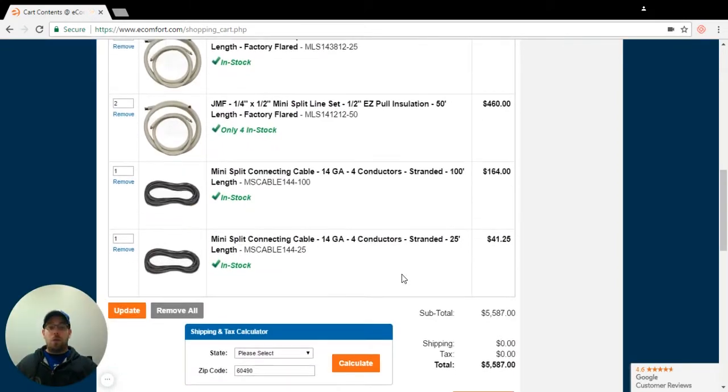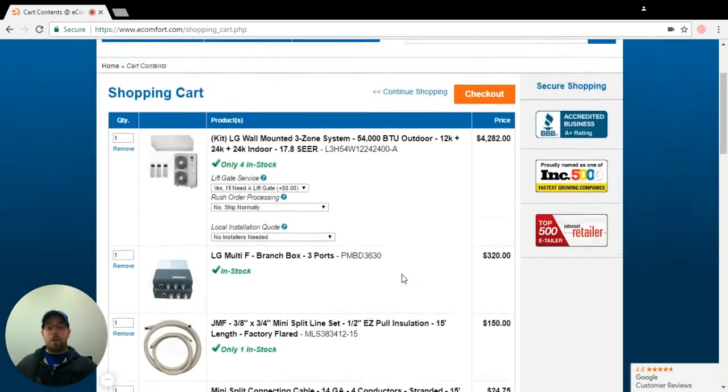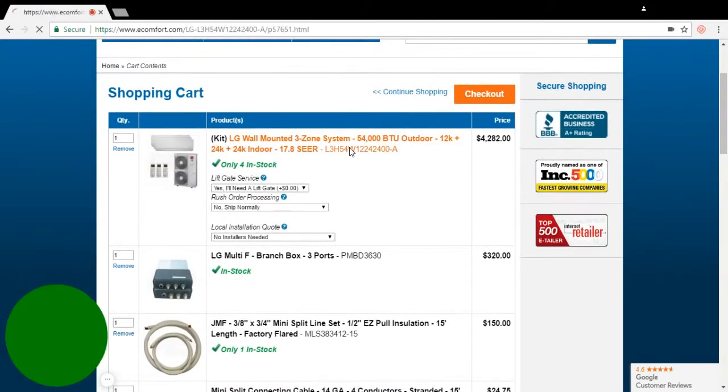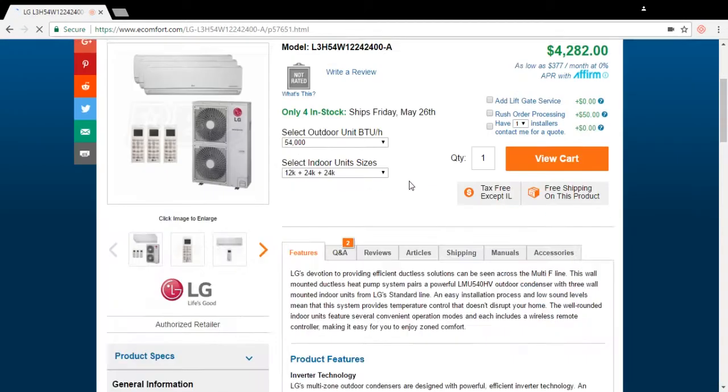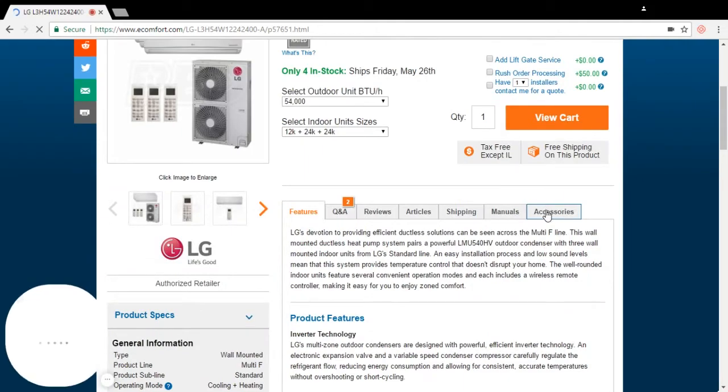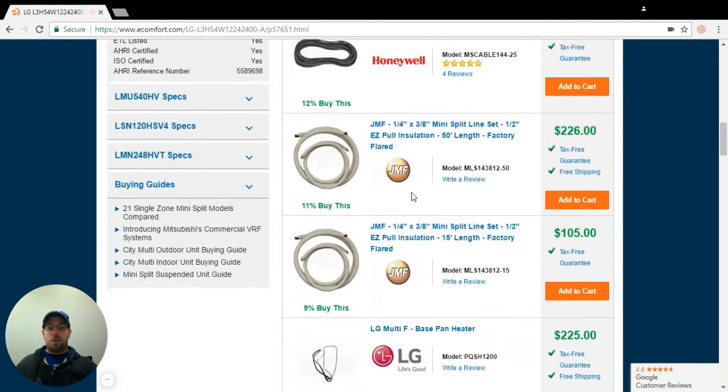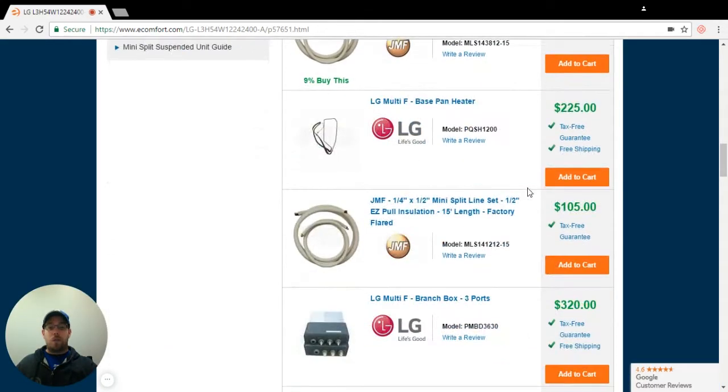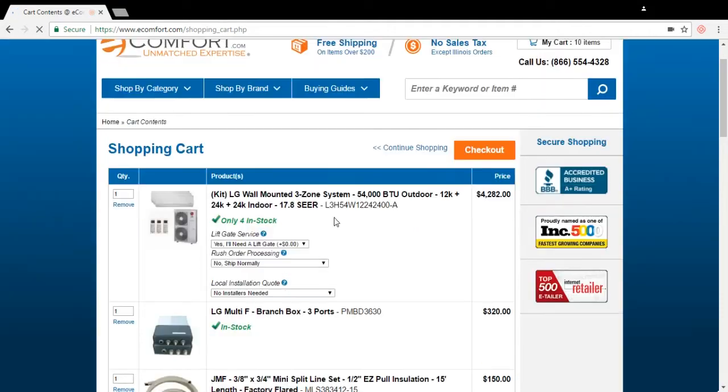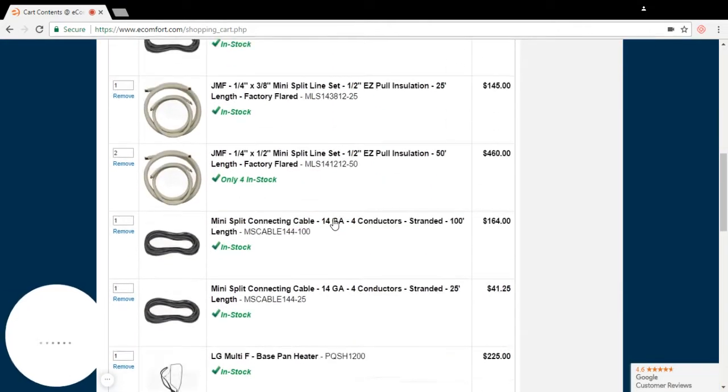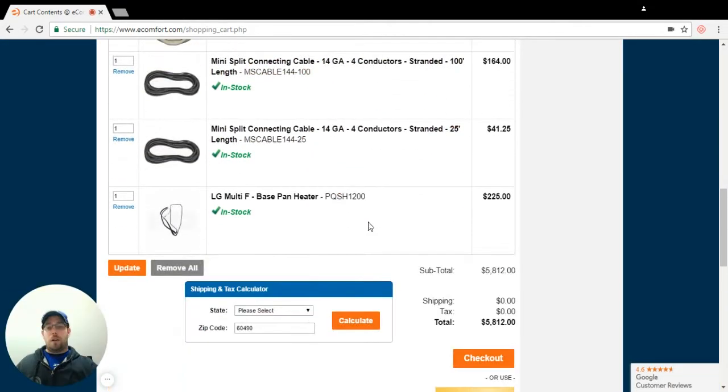Other things that are required for this unit, especially if you're in a cold climate, you're going to need a drain pan heater. Anytime that you get below 30 degrees, we do suggest that you purchase the drain pan heater because some warranties require that you have it. I'm going to put the drain pan heater on here because we're in Chicagoland area and we get darn cold.